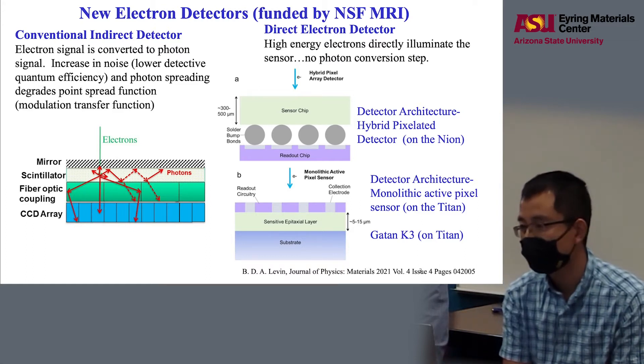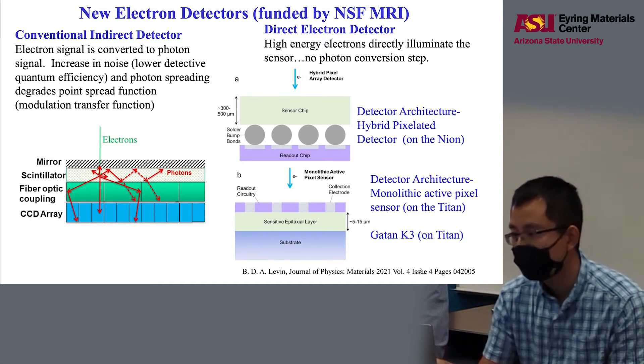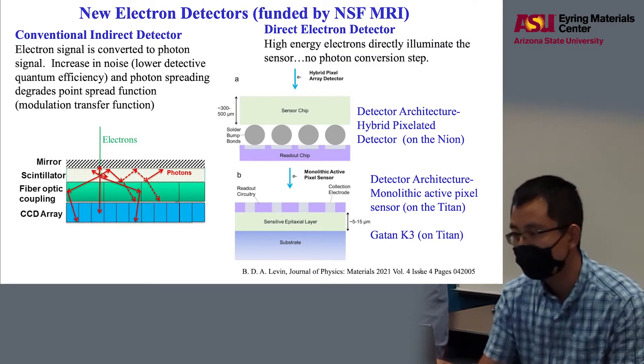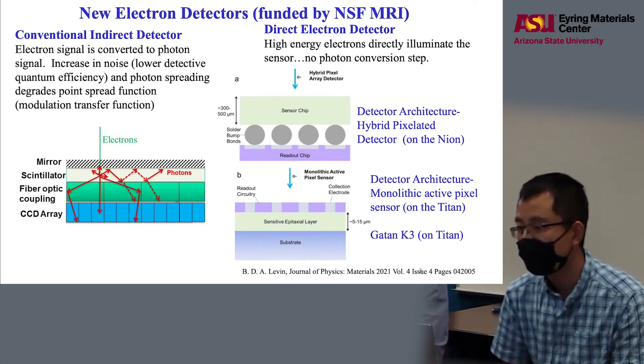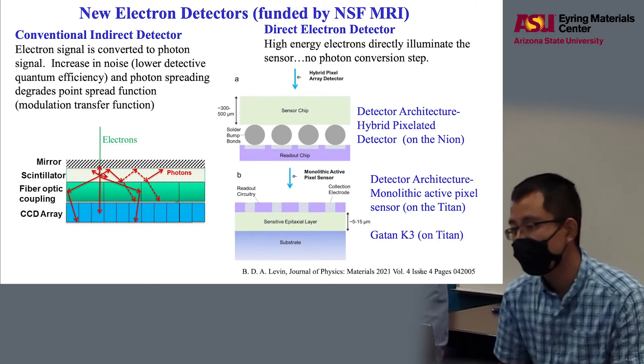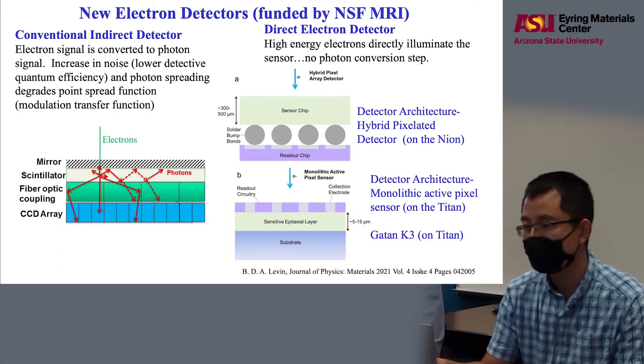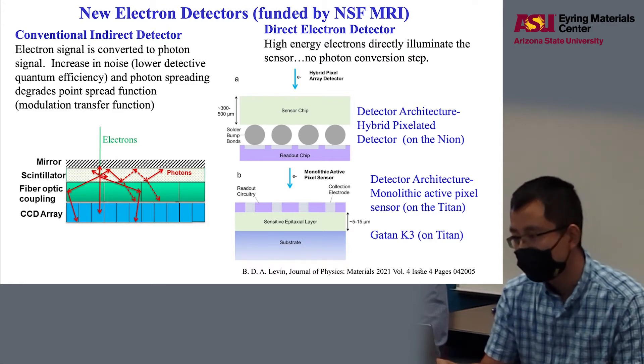There are two different types of direct electron detectors. For example, we have introduced a detector on the Nion microscope. It is a hybrid pixelated detector, where the electron goes to a sensor chip and then to the readout chip. The benefit of this design is that it is sensitive to low voltage. So the Nion microscope can do good EELS and also diffraction imaging under 30 kV, 60 kV, and 100 kV.